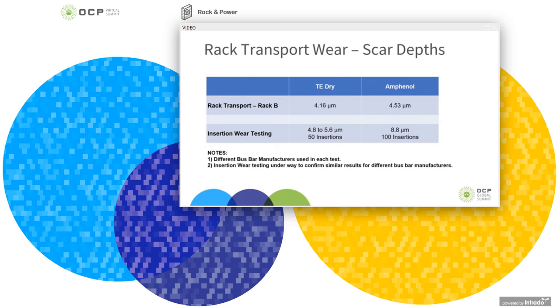Yeah, that was what was interesting to me, because I actually thought that the rack transport test really wasn't that bad, and that the insertion wear was really the problem. But when we looked at the TE dry results from the wear testing, and at what we thought visually was the worst TE dry, you can see that it was kind of similar to 50 insertions. And when we looked at Amphenol, which was the other connector in the rack transport testing, you could see that the Amphenol scar was also about equivalent to 50 insertions. We can't quite draw that conclusion because different bus bar manufacturers were used in each test.